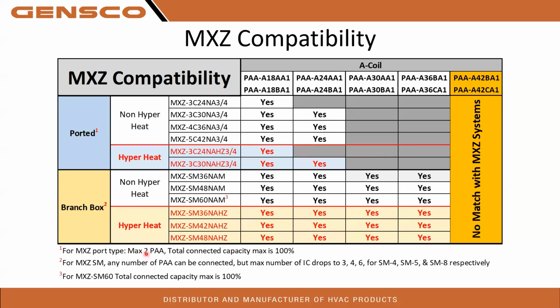On the ported style systems, maximum of 2 coils. Make sure you don't exceed that if you have a 3C, 4C, or 5C. You can only have 2 of the indoor coils, and your total connected capacity is restricted to 100%. It means you cannot oversize for the heat pump. If you're going off the 130% rule, that will not apply with the Hyper Heat coils. Have to stay to 100%.